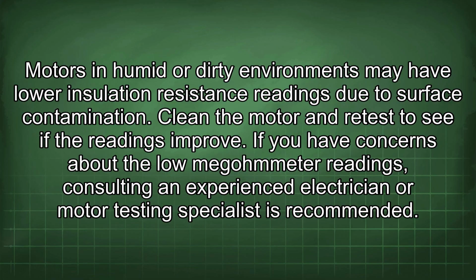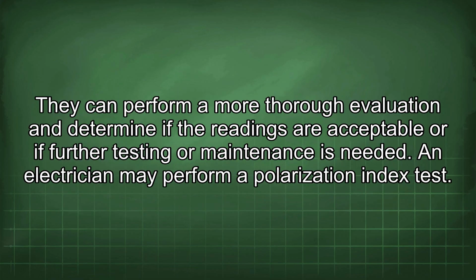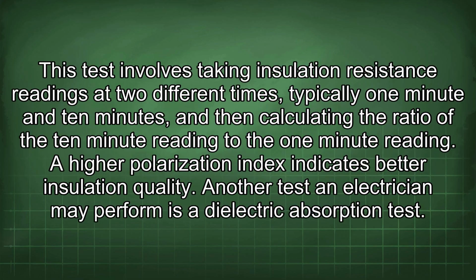If you have concerns about the low megohmmeter readings, consulting an experienced electrician or motor testing specialist is recommended. They can perform a more thorough evaluation and determine if the readings are acceptable or if further testing or maintenance is needed. An electrician may perform a polarization index test. This test involves taking insulation resistance readings at two different times, typically 1 minute and 10 minutes, and then calculating the ratio of the 10-minute reading to the 1-minute reading. A higher polarization index indicates better insulation quality.